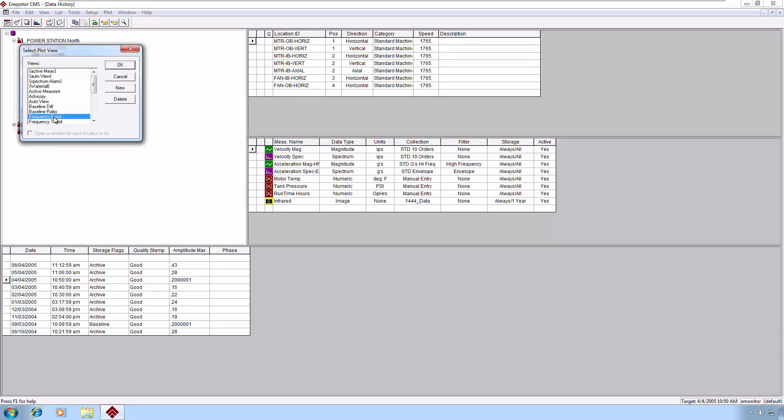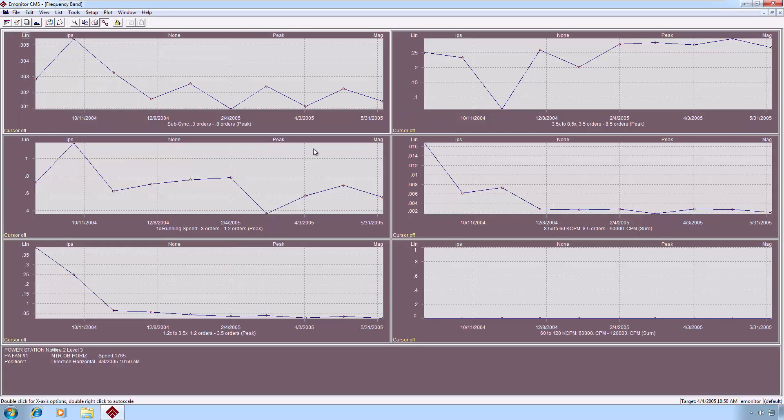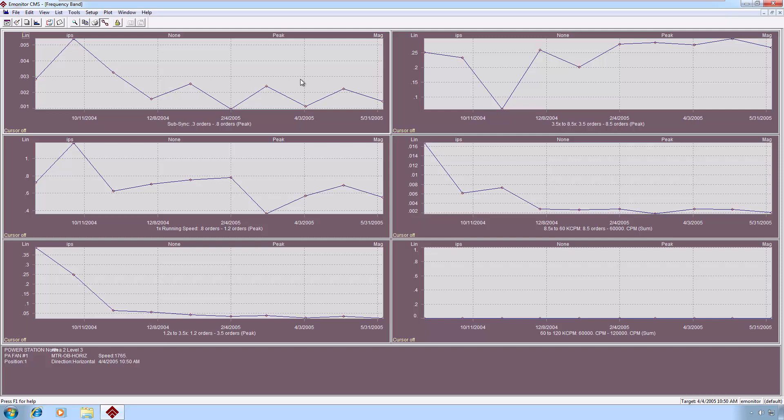If we take a look at the frequency band, it will give us a plot pane for each frequency band in the band set that we have set in the particular machine category for this measurement. E-Monitor uses categories to control a variety of things, but you can assign alarm thresholds based on the category and the particular band set that you've chosen. This is a standard six-band set, and so it gives us the trend of the energy in each one of those six bands.